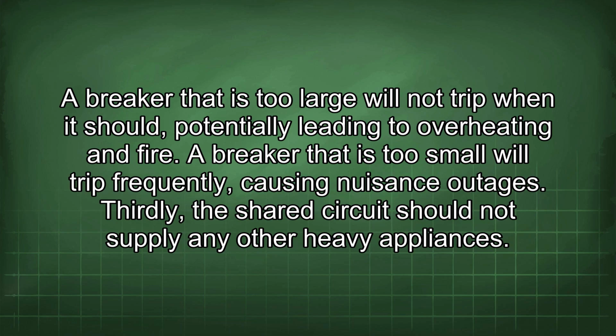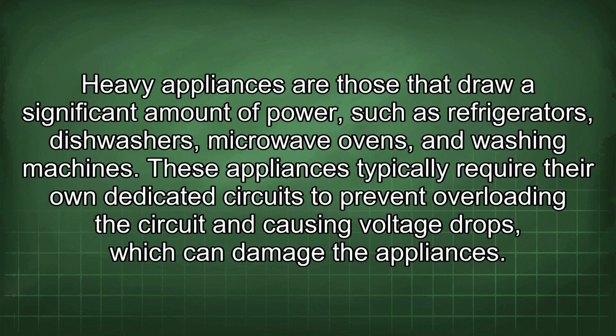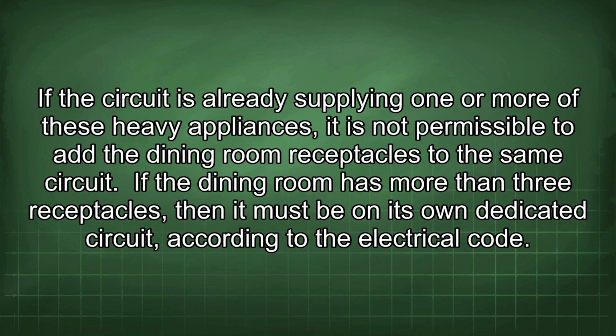Thirdly, the shared circuit should not supply any other heavy appliances. Heavy appliances are those that draw a significant amount of power, such as refrigerators, dishwashers, microwave ovens, and washing machines. These appliances typically require their own dedicated circuits to prevent overloading the circuit and causing voltage drops, which can damage the appliances. If the circuit is already supplying one or more of these heavy appliances, it is not permissible to add the dining room receptacles to the same circuit.